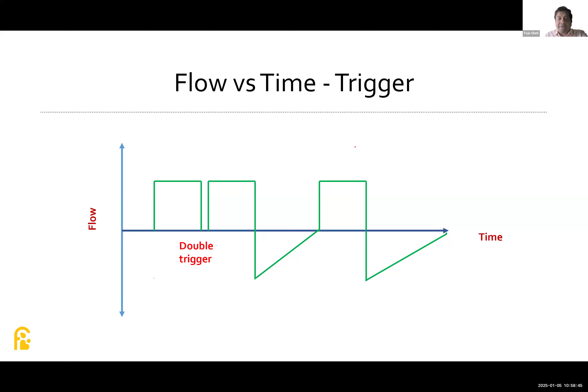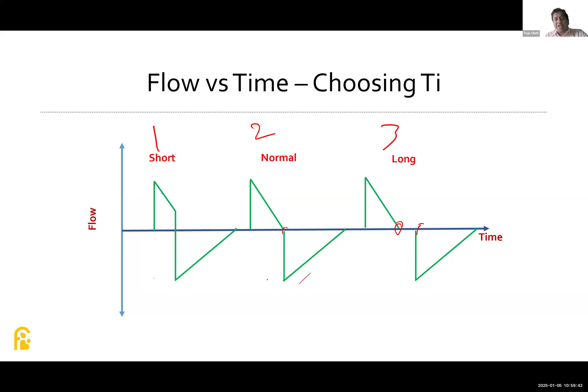Graphics will also help you to choose the ideal Ti. What is the ideal Ti among these three? Obviously the center one. Why am I saying it? Because once the inspiration has stopped, immediately the expiration is starting. What is happening in the first? The inspiratory flow has not come to zero and the expiration has started. What is happening in the third? Inspiratory flow has come to zero, but the expiration is not getting started. So this is normal. Here it is very short. Here it is very long. So you will be able to choose the ideal Ti, or near ideal Ti we can say, or optimal Ti for that baby if you are using these types of graphics.